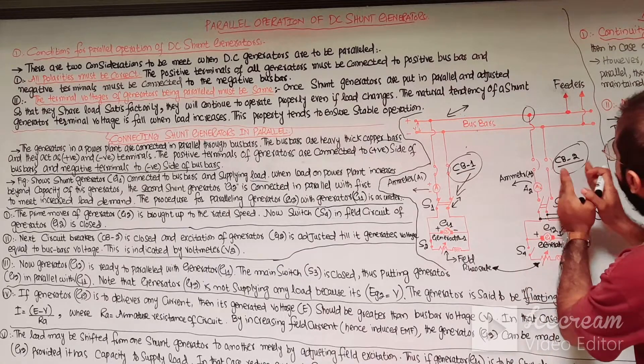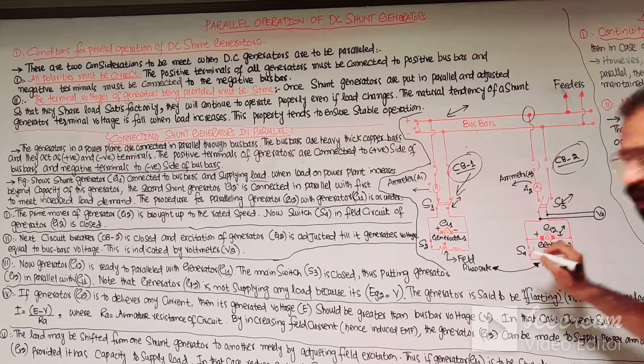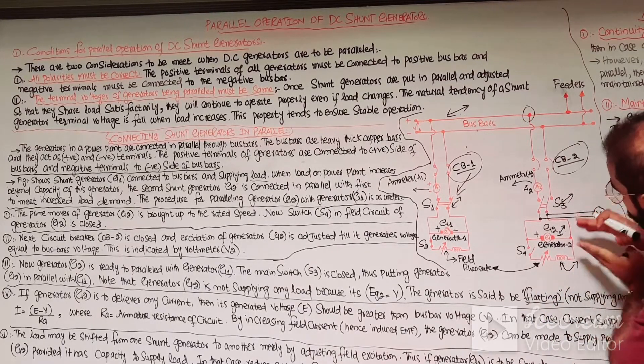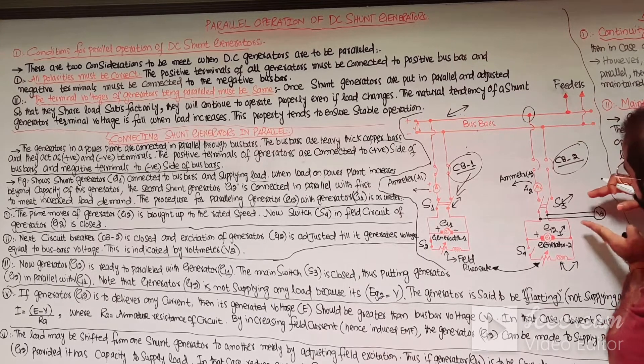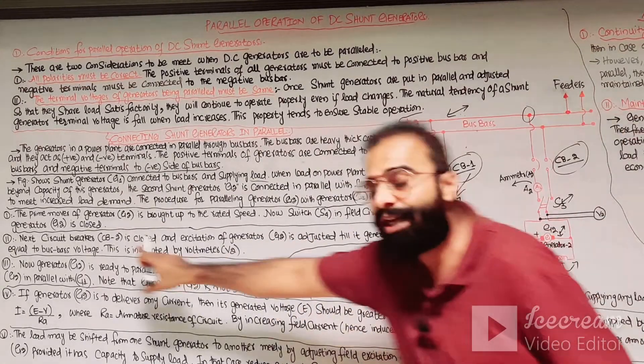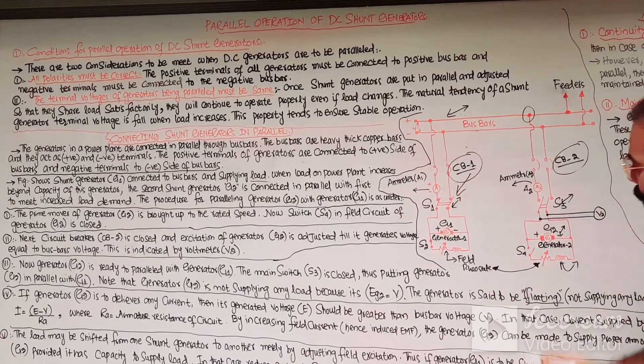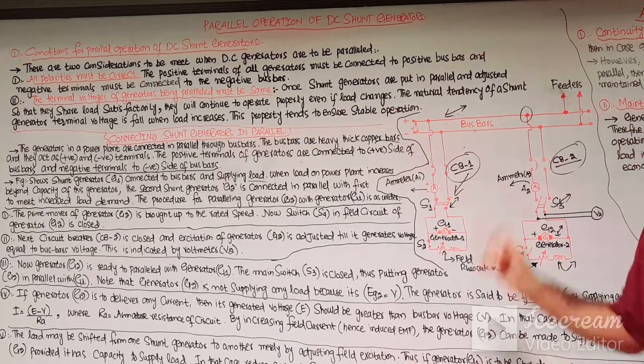The second step is to close the circuit breaker of the G2 generator and adjust the excitation of the G2 generator's field circuit until the generated EMF of G2 is equal to the bus bar voltage. This terminal voltage is measured with the help of a voltmeter connected in parallel across the terminals of the G2 generator.